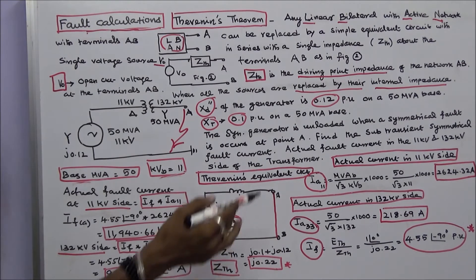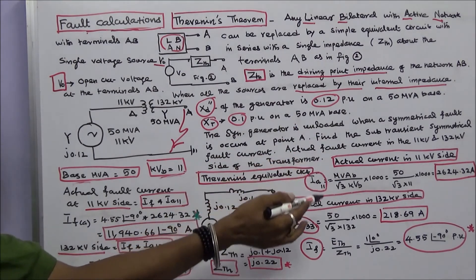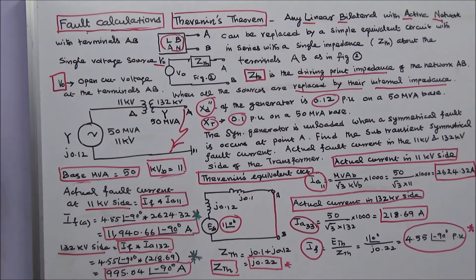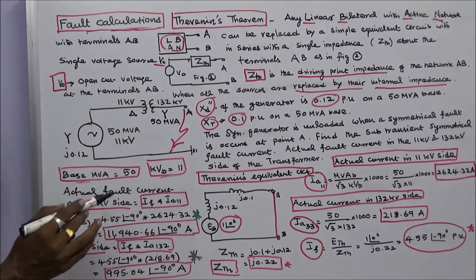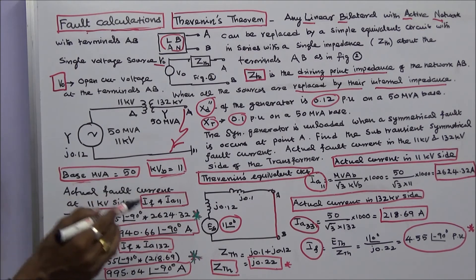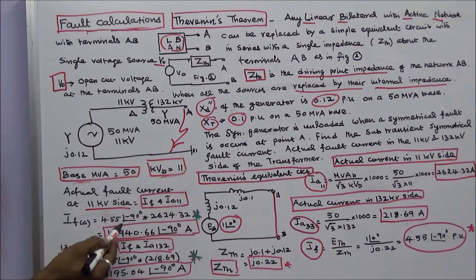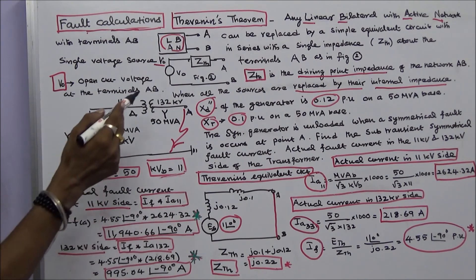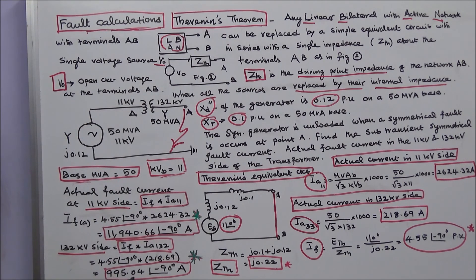Knowing the fault current and the actual base currents, I can calculate the actual fault current in the 11 kV side and the 132 kV side. Actual fault current in the 11 kV side is equal to per unit fault current into actual base current in the 11 kV side. Fault current is 4.55∠−90°, and actual base current in the 11 kV side is 2624.32 Amps. Therefore actual fault current in the 11 kV side is 11940.66∠−90° Amps. Similarly for the 132 kV side: fault current 4.55∠−90° into actual base current 218.69 Amps gives actual fault current in the 132 kV side as 995.04∠−90° Amps.